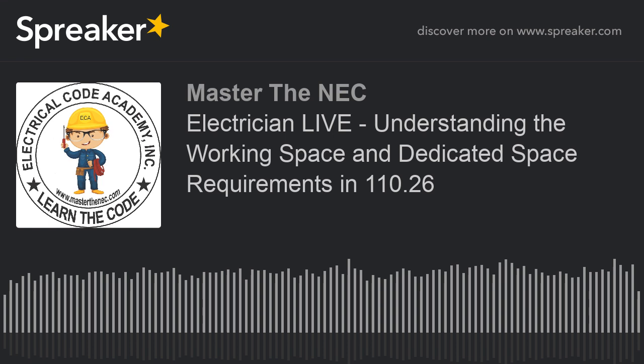So can I have sprinkler protection? Absolutely. In that space, I can have that in my 6 foot space. But if I do so, I still have to follow the rules for protecting it against possible leakage and things like that over my equipment. Okay? But remember, we're talking equipment space. We're not talking anything in our working space. Keep the two separate deals, folks.